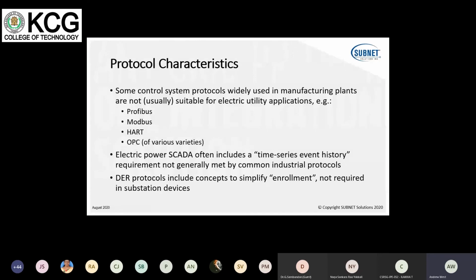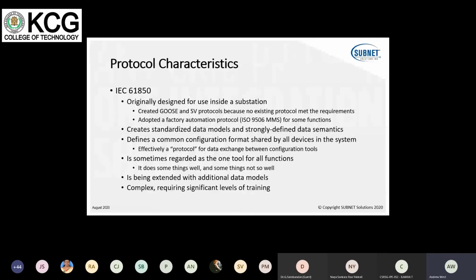So, some brief high-level overview. 61850 was originally designed for use in the substation. It's now being promoted for use externally across all power grid functions. 61850 created the GOOSE and sampled value protocols because they had requirements that no other protocol could meet. So here's an example of creating something if you need to, because nothing else will do the job.